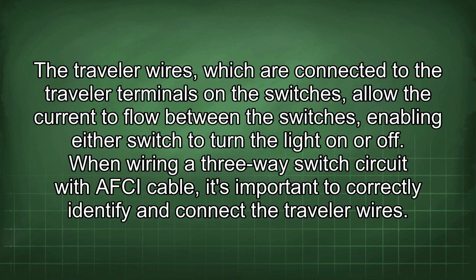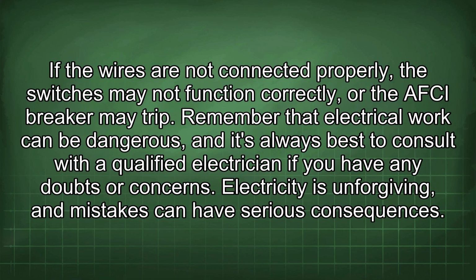When wiring a three-way switch circuit with a AFCI cable, it's important to correctly identify and connect the traveler wires. If the wires are not connected properly, the switches may not function correctly, or the AFCI breaker may trip. Remember that electrical work can be dangerous, and it's always best to consult with a qualified electrician if you have any doubts or concerns. Electricity is unforgiving, and mistakes can have serious consequences.